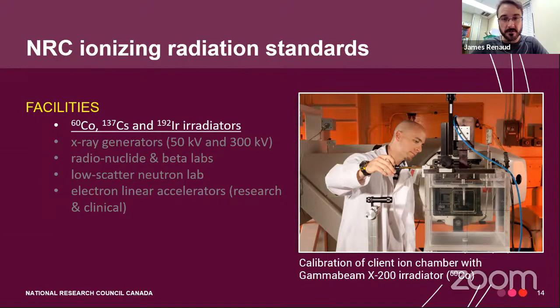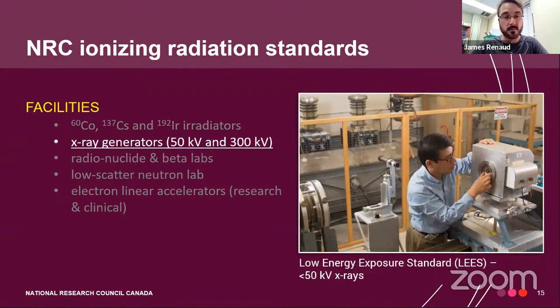The microSelectron afterloader can deliver the HDR iridium sources with air kerma rates of between 1 to 50 milligray meter squared per hour, and that depends on the time of year. And the HDR facility can also provide calibration services for the therapy class well chambers. We also are equipped with low and medium energy X-ray generators that provide stable beams of X-rays at constant potentials from 10 kV to 300 kV. Exposure rates covering both protection and therapeutic levels can be selected. The X-ray facility can provide calibrations, again, for therapy class chambers, radiation protection devices, as well as custom services, which can be arranged.